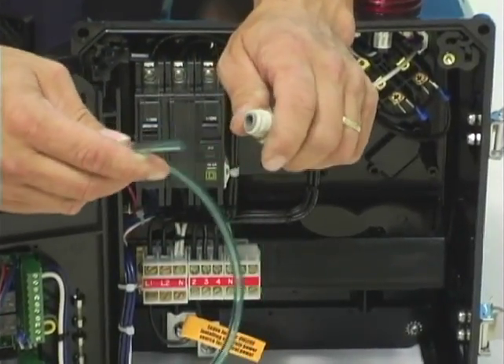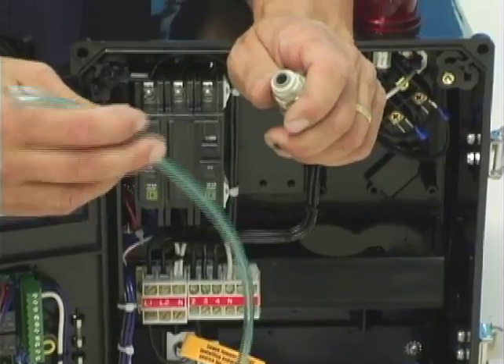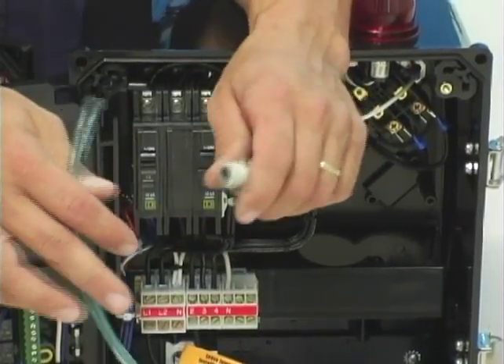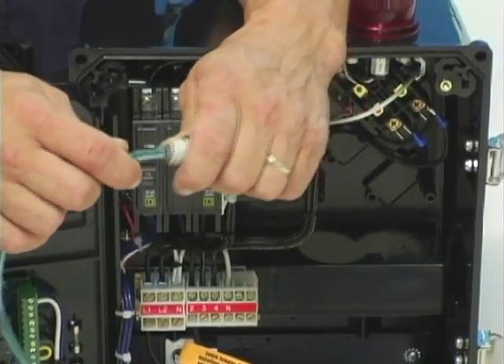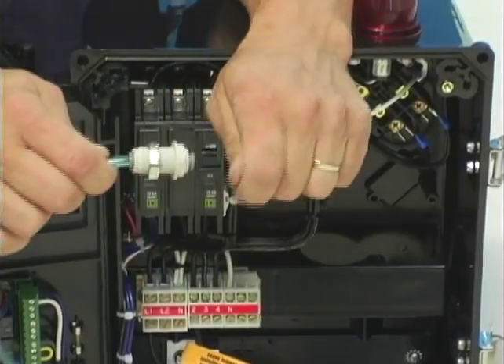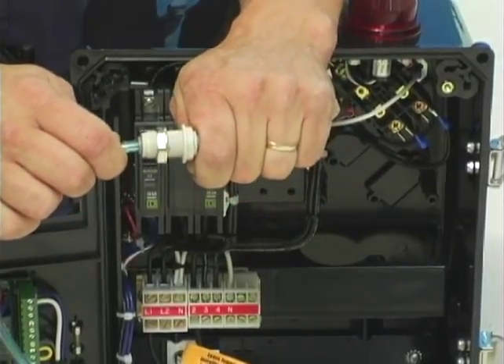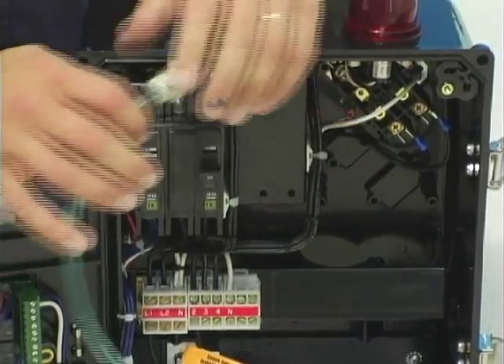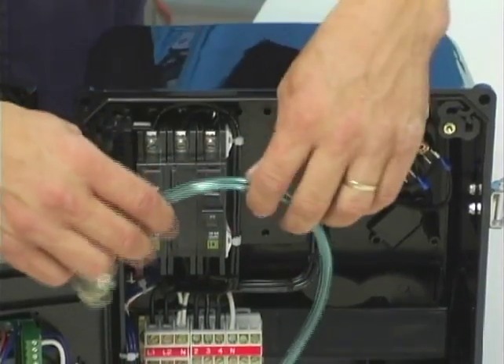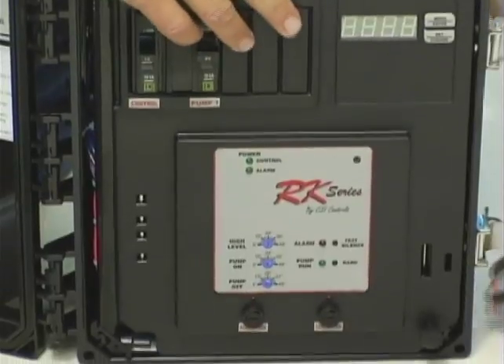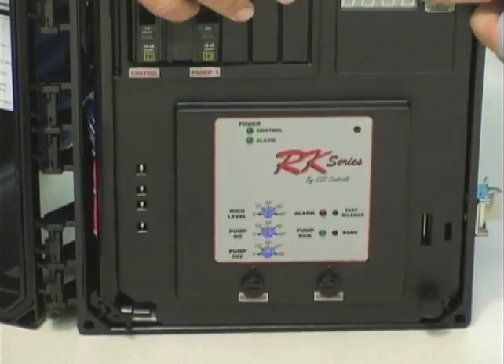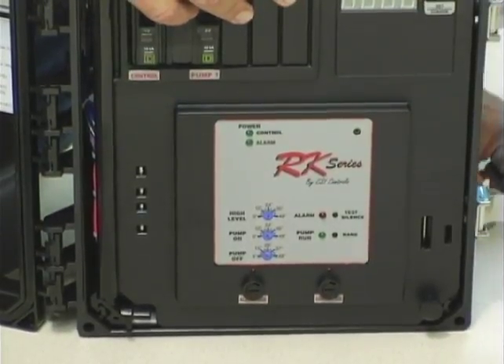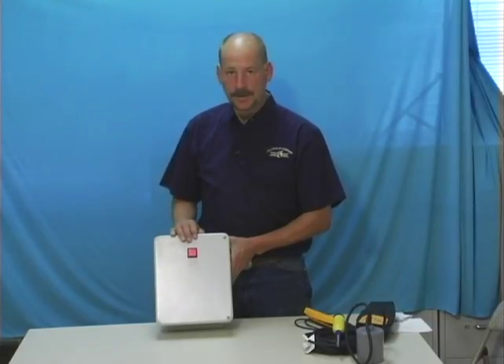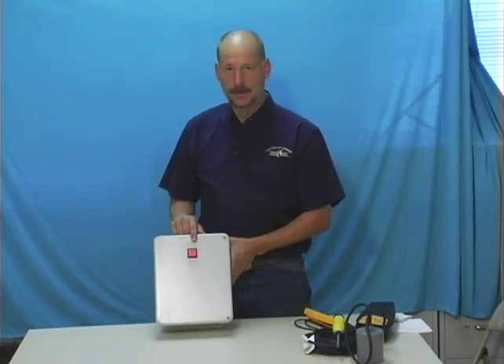Let the control panel catch up basically with itself, get zeroed back out. Reattach the tubing, reattach the other half of the tubing that's going out to the wet well, turn the control panel on, push the pressure bell back down into the water, and you should start getting a reading on the digital display.